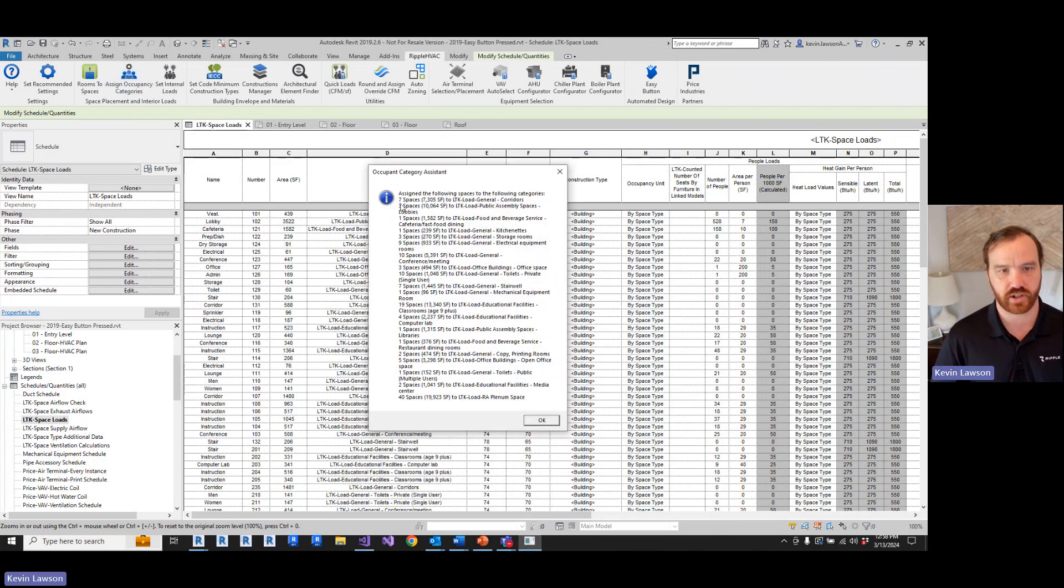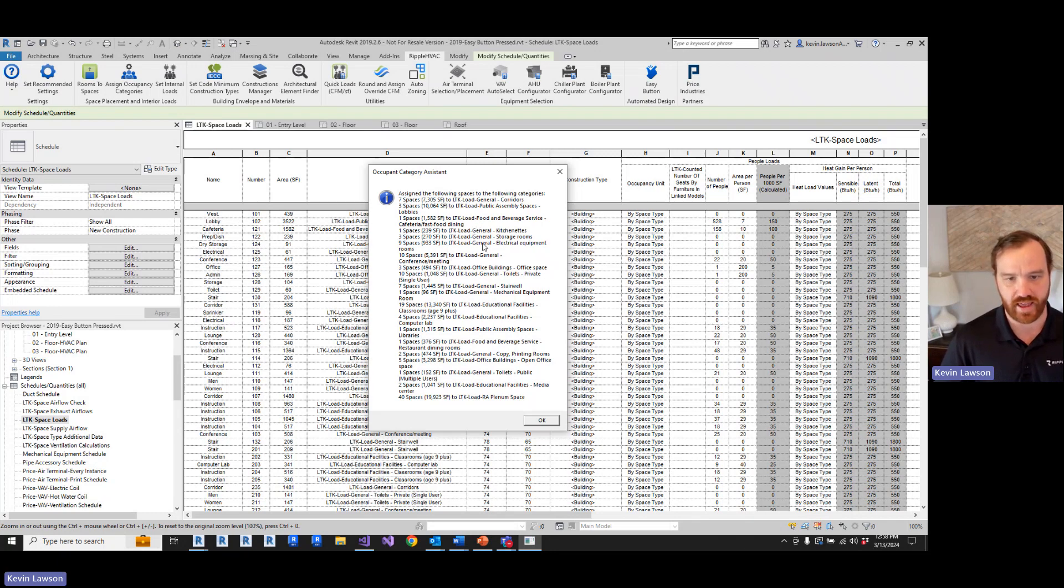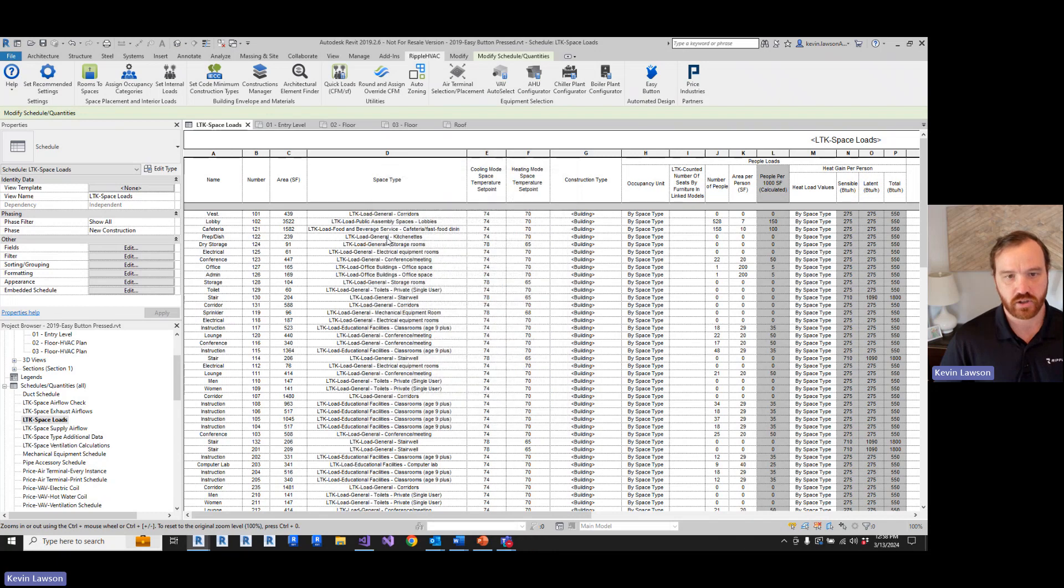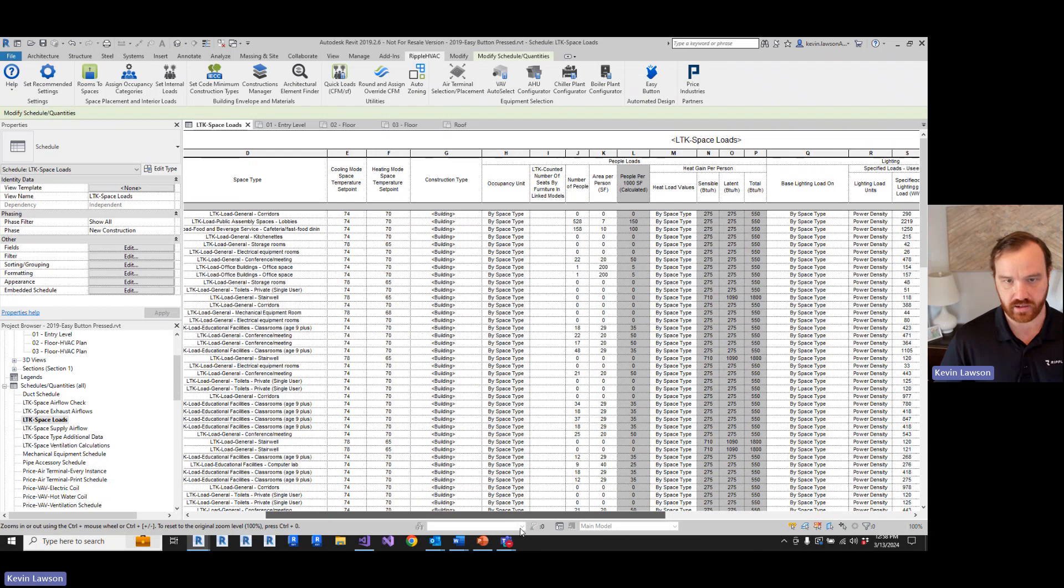So this is gonna go through, it's gonna read the architectural room name and the area and try to parse out an ASHRAE 62.1 space type and apply that. So once it applies that, now all of our internal loads are set.